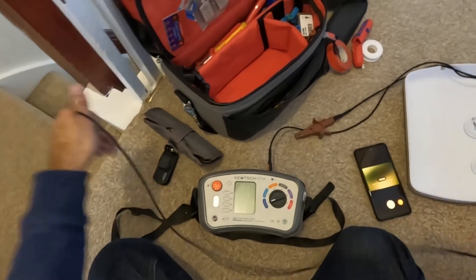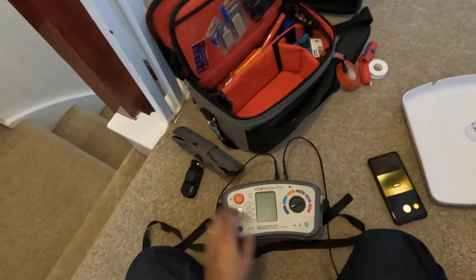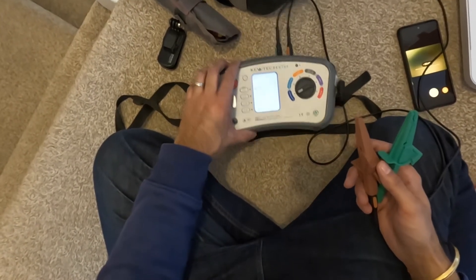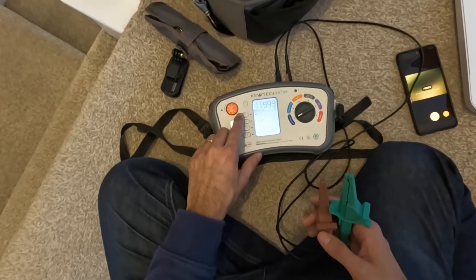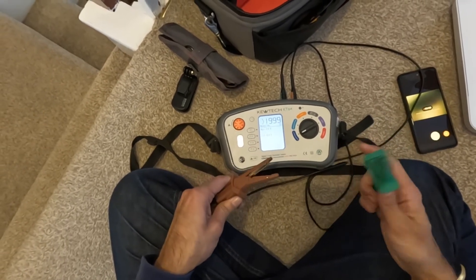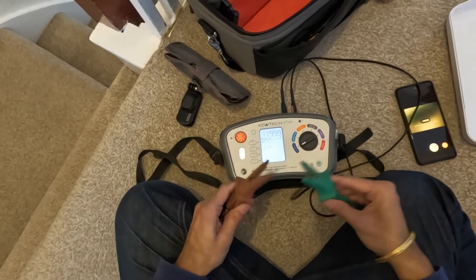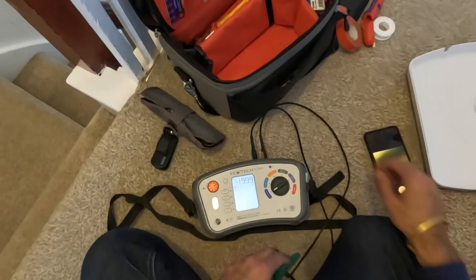I'm using crocodile clips — one for the green earth terminal and one for the live which is the brown wire. This is the Kewtech KT64. I press the null button first to reset it and it measures the resistance on the leads, then tick the null function so the meter takes out the lead resistance — now when we measure it'll be more accurate.